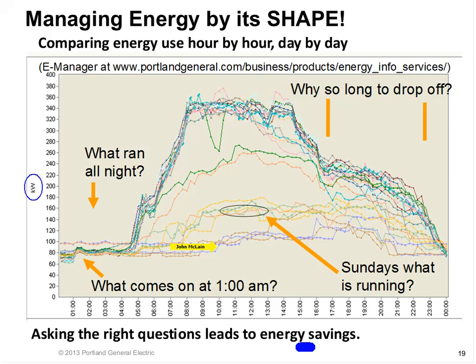So let's look at the questions that I was told this customer was asking. I like this one right here. The question was, I can ask a very smart question: what comes on at 1 a.m., bump in the night, and stays on for the whole night? And the answer was, the IT department finally came up and said, we think it's us. We run computer backups every night at 1 a.m. We bought some software. It automatically turns on all the computers and runs backups and diagnostics and those kinds of things. When asked how long does that take, they said about 45 minutes.